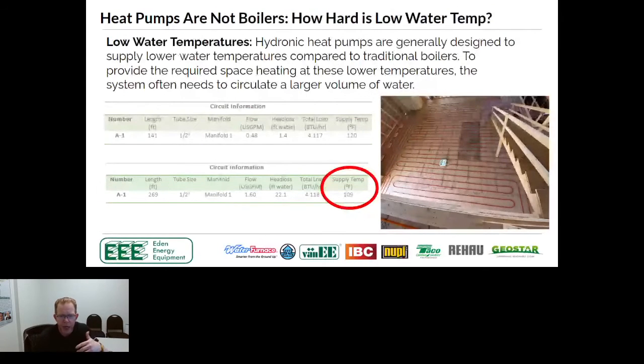So as we look at it and say, how hard is it for us to design for a lower water temperature? I get this question asked a lot. This was a real world customer scenario. So in this case, all we did to get the supply water temperature in this new install was we added 100 feet of pipe. So PEX pipe, 35 cents a foot, somewhere in that neighborhood, even if you said 50 cents a foot, who cares? So for you to add $100 of material to this job, what that means is you took a unit that might have had a COP of 2.5, i.e. 250% efficient. You were able to bring that water temperature down to 109 degrees. So now it's over 300% efficient. Where I'm going with this is don't get stuck so much on material costs.